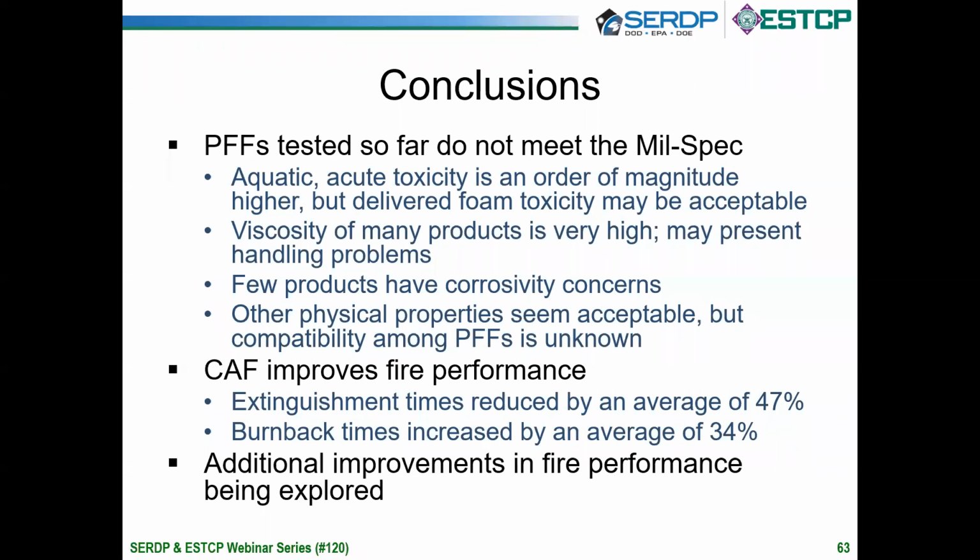We do know that compressed air foam does improve fire performance quite significantly, both in terms of extinguishment time and the burn back time, but we still need additional improvement. And so we're going to optimize these two techniques. We're going to additionally look at some additives to meet the spec as it exists now.